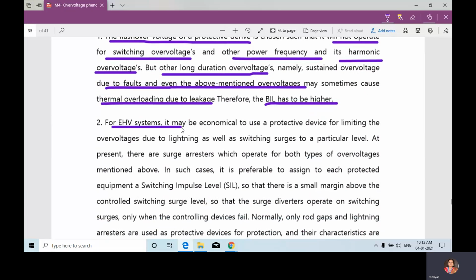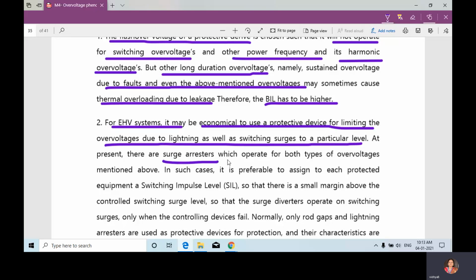Next, for EHV system, it may be economical to use a protective device for limiting the over voltages due to lightning as well as switching surges to a particular level. In extra high voltage system, it is economical. Okay, a protective device for limiting the over voltage due to lightning and switching surges. There are surge arresters. What does it do? It will operate for both types of over voltages, due to lightning and switching surges.